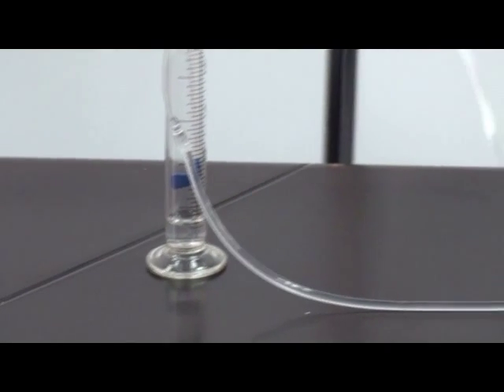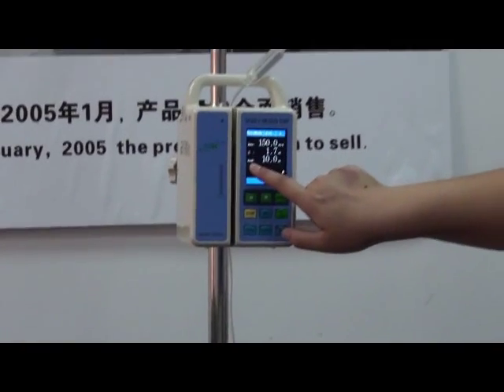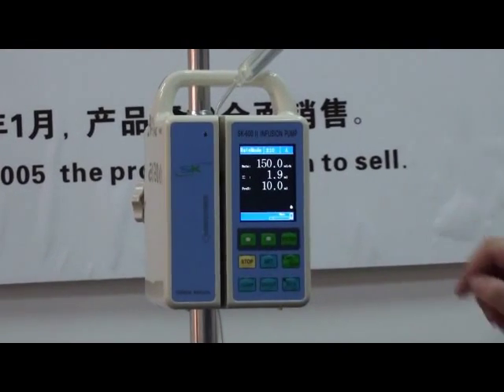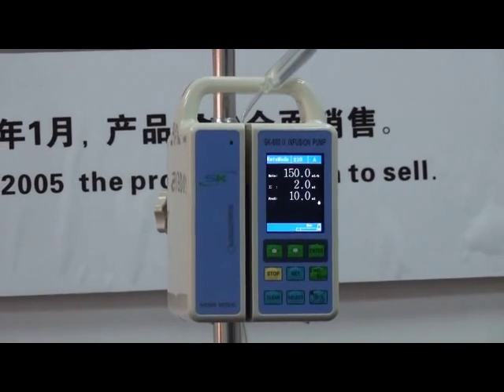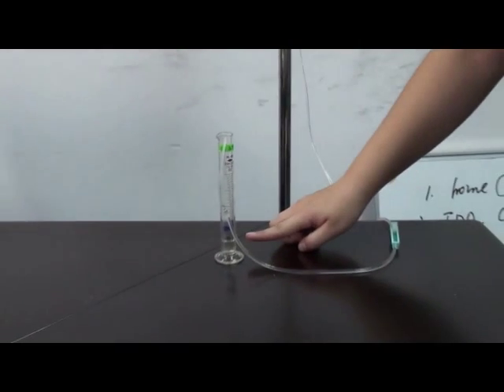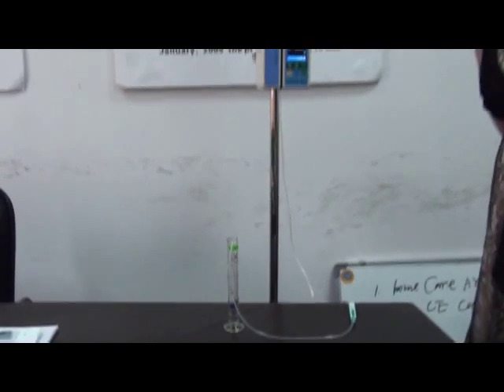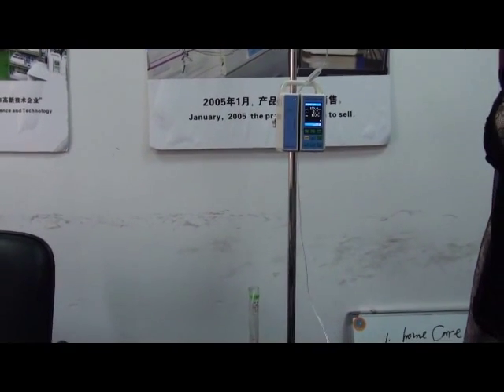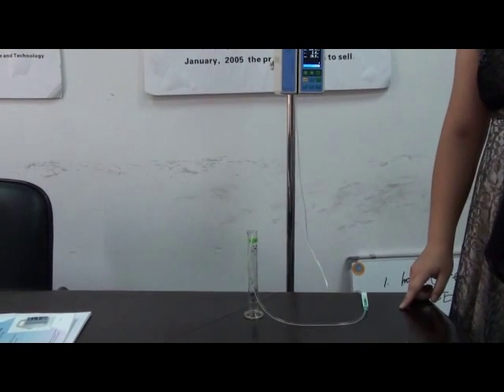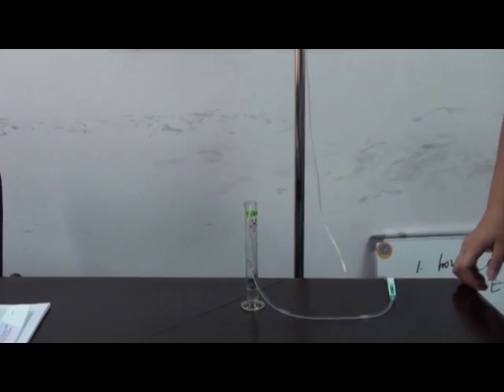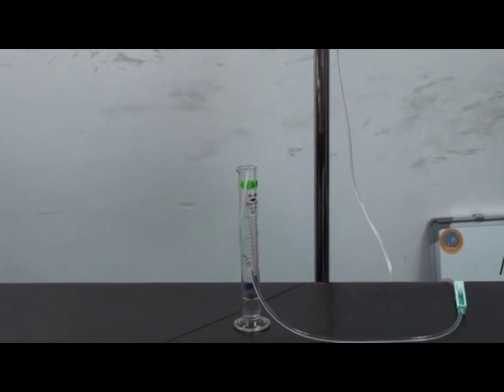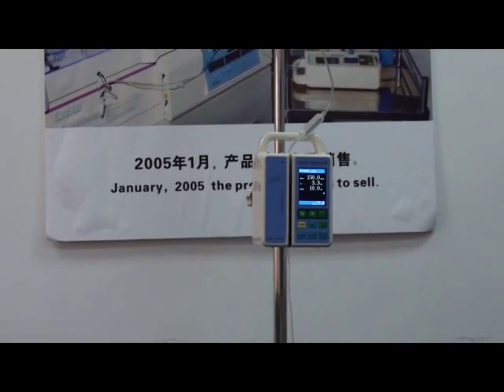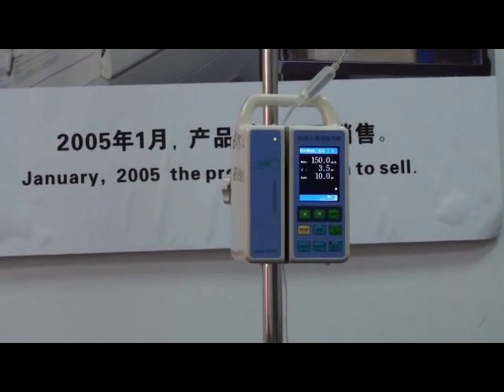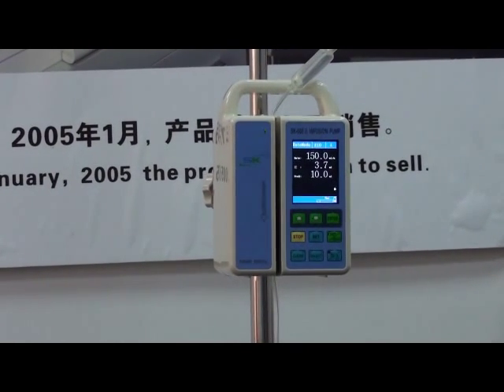I need to explain about the theory here. You will see we set the preset volume to be 10 ml, right? If the IV set works accurately, the actual volume should be 10. I mean, it should be exactly the same as the preset volume we set. But if the accuracy value is not good, the actual volume may be maybe 12, maybe 8. I mean, it will not be 10, right? If it is like this, you need to change the accuracy value. Generally speaking, if the preset volume is 10 and the actual volume is 11, suppose it is 11, 1 ml more than 10, we will add 2 to the accuracy value.